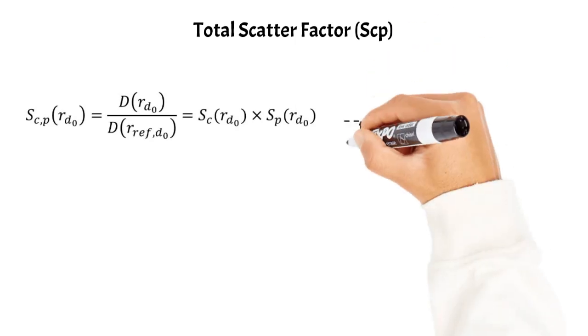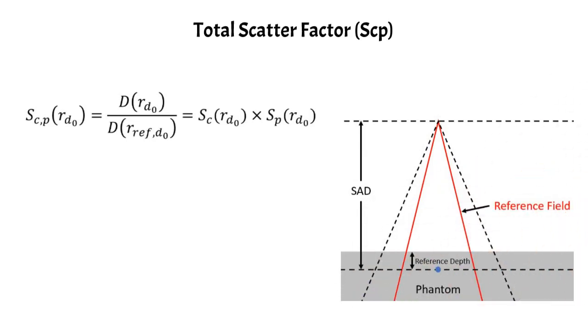Now we can talk about the total scatter factor, or Scp. It's a ratio of doses — one with field size r, defined at a depth of d0 in the phantom, and the other with field size r ref, also defined at depth d0. It is also defined as the product of the collimator and phantom scatter factors. On the right is the geometry used when measuring the total scatter factor — it's measured at SAD, at a reference depth, and is the ratio of doses measured with the collimated field size (the black dotted line) and the reference field size (in red).